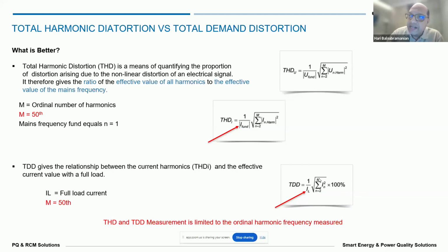Later, as the IEEE 519 standard evolved, they also introduced a term called TDD, total demand distortion. Total demand distortion is only for current, not for voltage, and it is based on a value called IL. IL is basically the average current over a period of time. For example, a 12 month average is considered as the load current.